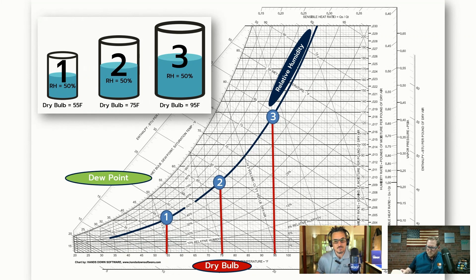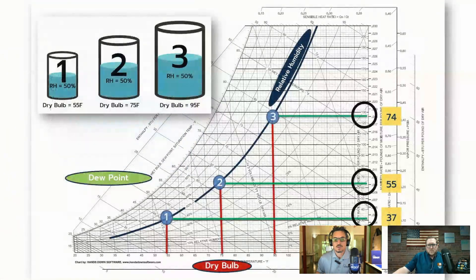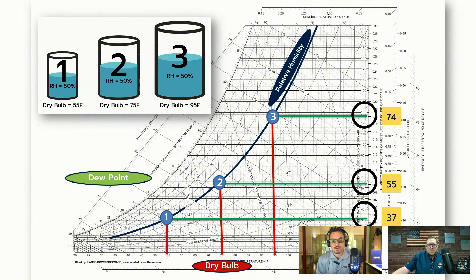Dewpoint is a great way to track the actual amount of humidity in the air — it's not relative to the temperature. You can see the dewpoint here, here, and here. The dewpoint of container one is 37, and the dewpoint of container three is 74. This illustrates that dewpoint is a much better number to show the actual amount of moisture in the air.